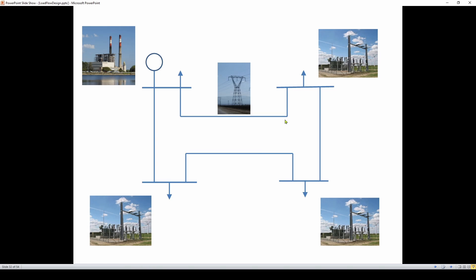We also talked about not just a static simulation but what's called a dynamic or stability simulation — where you simulate what happens if you take something out of service and how the network responds instantaneously. Kind of like driving your car and slamming on the brakes: how long does it take to stop? In a power system, if a load trips off, you simulate how the system will respond, keeping in mind that generators are big massive rotating machines with inertia — will the system handle it or go out of service?